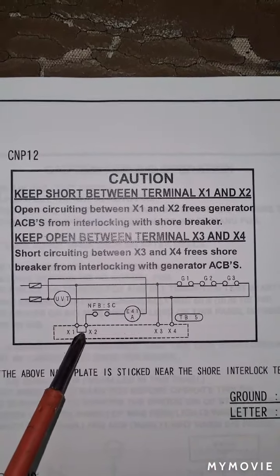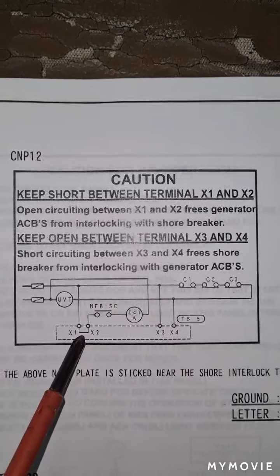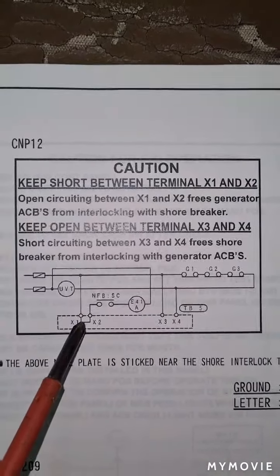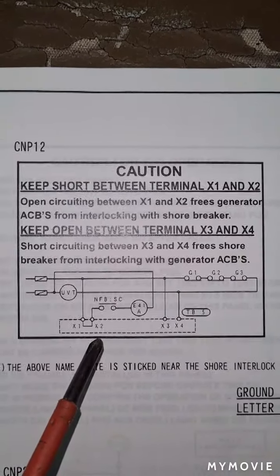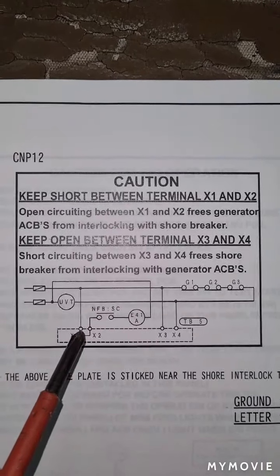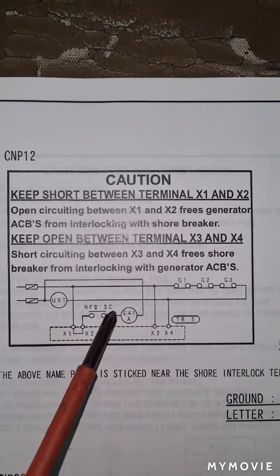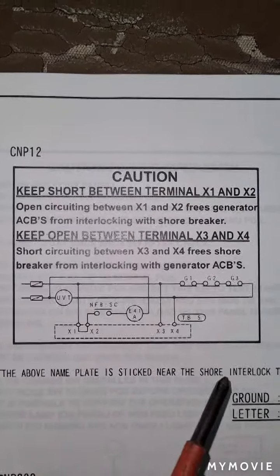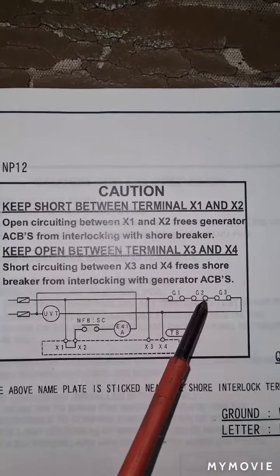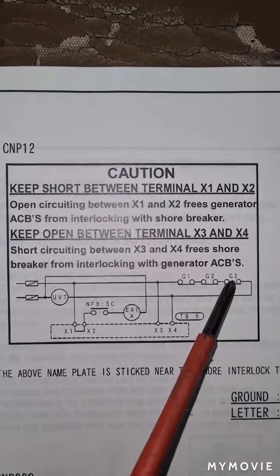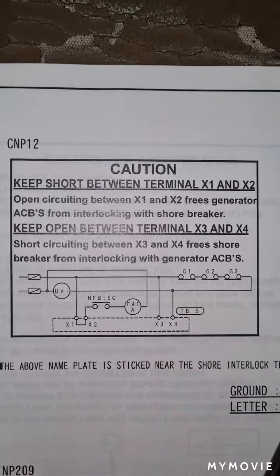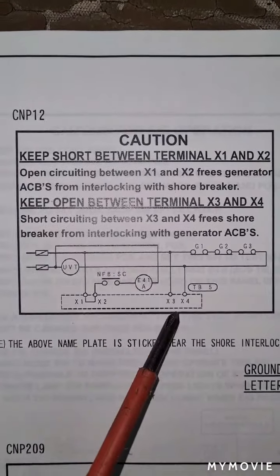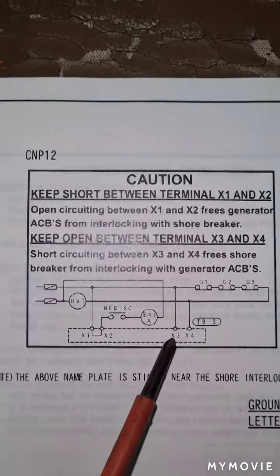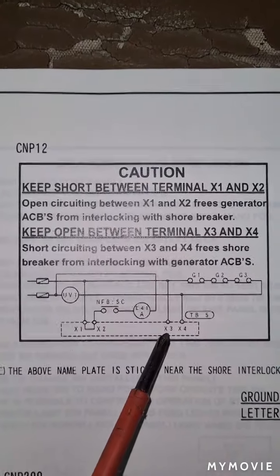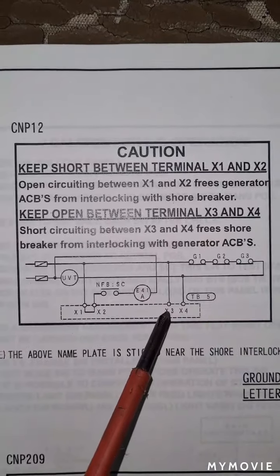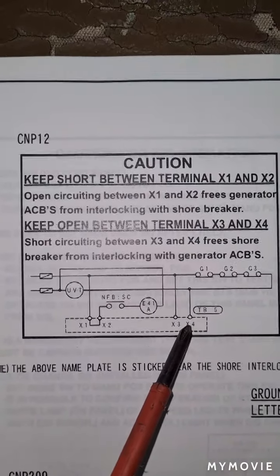Never try to remove the shorting wire for X1 and X2, because if you do so, you will disable the safety interlocking of your shore connection circuit breaker with the generator 1, generator 2, and generator 3 air circuit breakers. Also here are the X3 and X4 terminals. These X3 and X4 terminals are always open.